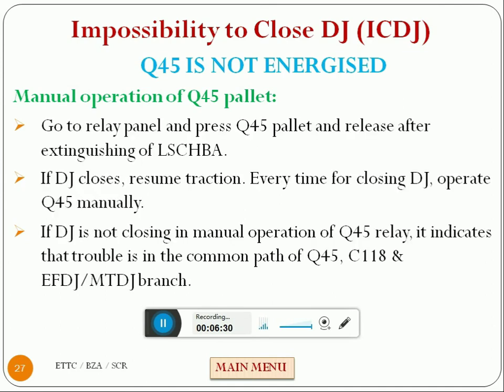So close BLDJ, ensure ZPT on one position. Press the Q45 pallet manually until LSHB extinguishes. After extinguishing LSHB, release the Q45 pallet. If successful, work further by operating Q45 manually for every closing of DJ. If DJ trips after releasing the Q45 pallet, it indicates the trouble is in the other branches. With this, we have seen how to attend Q45 not energizing.